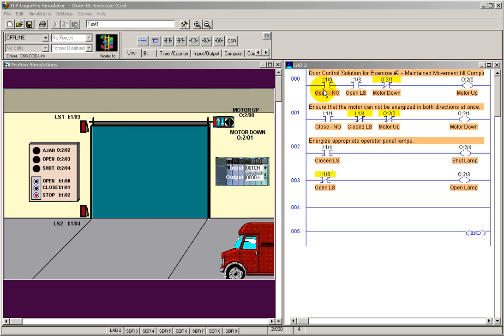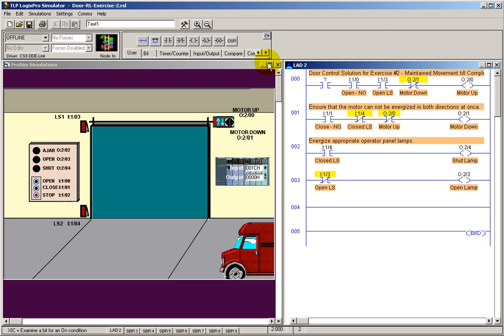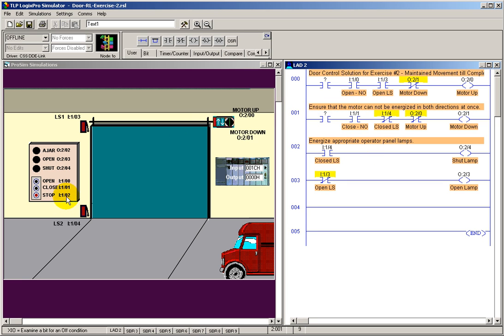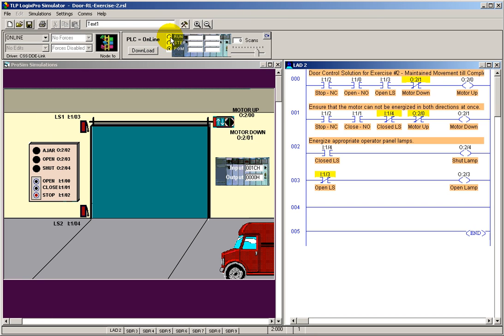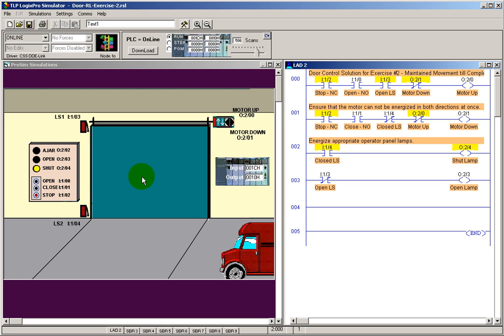Let's look at first adding two examine if closed instruction sets in rung zero and rung one. These will be our stop switches. Let's grab our stop, which is a normally closed push button. I've already put the symbol in and it's a normally closed. So this condition is normally satisfied. And if I quickly here just go to download this and run, you notice that both of these are true right now because this is a normally closed stop switch. This is looking for examine if true if closed. And it is closed. The only time it's going to be false is when it's open and that's when this stop switch is going to be activated.